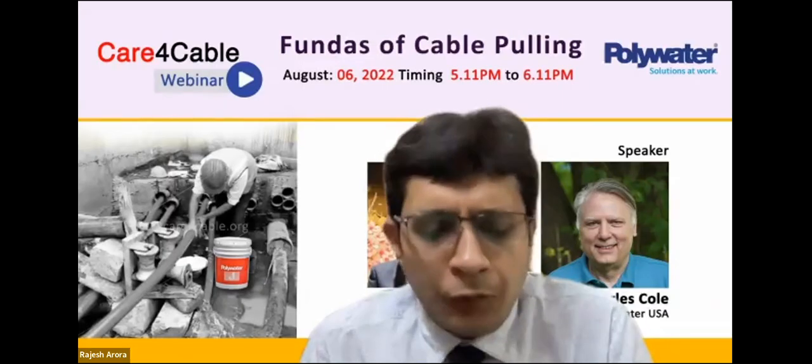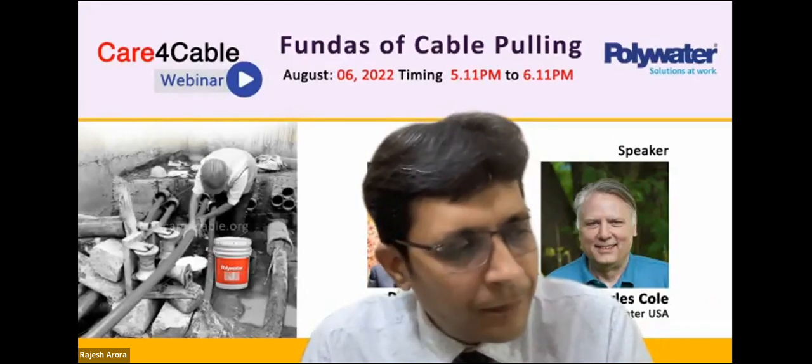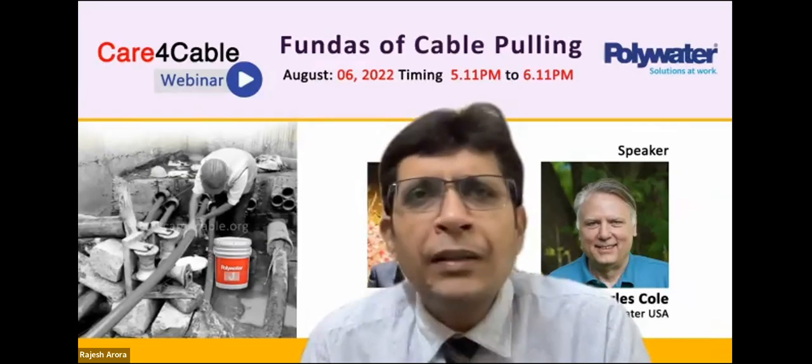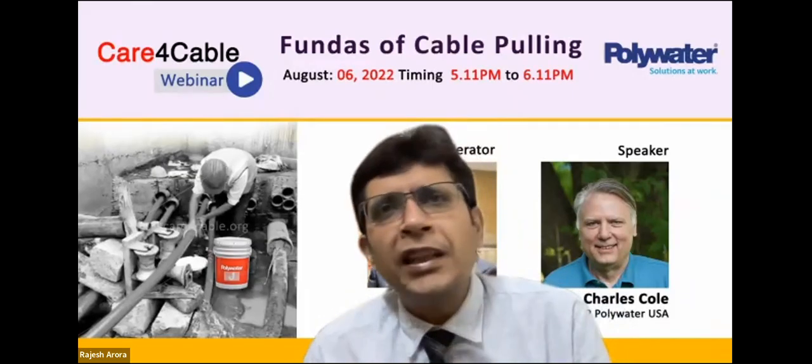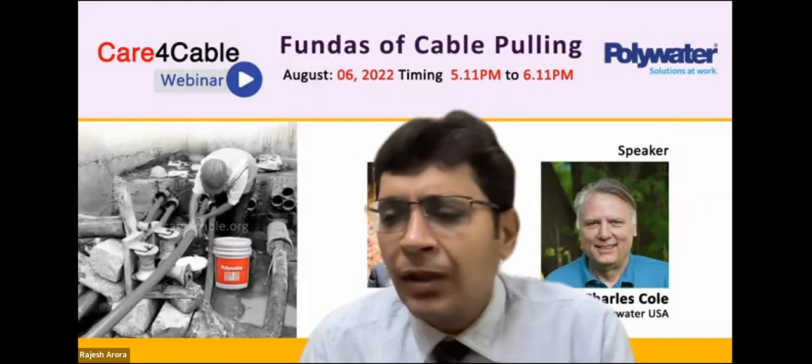And what is the problem you are facing? Our cable right now has an issue. It has a break somewhere, and it shows 330 meters from the point of supply. But in that particular area, there are more than 20 or 30 cables running along that cable. I can understand your problem is to pinpoint the particular point where that fault has happened.